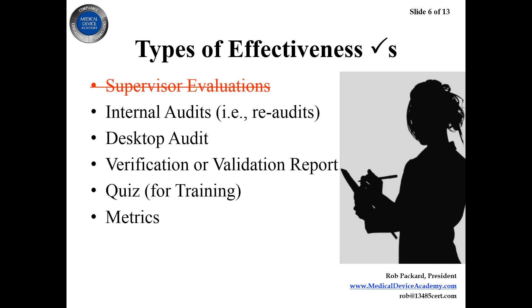One method the FDA likes to see — especially when there's an internal audit finding — is a re-audit. You had a non-conformity or a 483, you implement a CAPA, and then you go back and audit that one area; it might be a very short audit. But if the problem happened at a supplier in another state or country and you don't want to go on-site, you could do a desktop audit instead. That's another valid option.